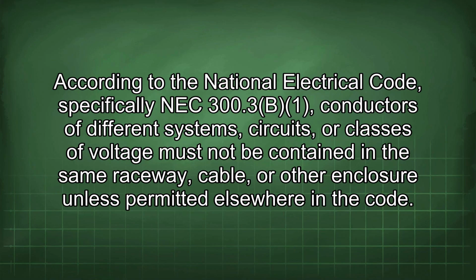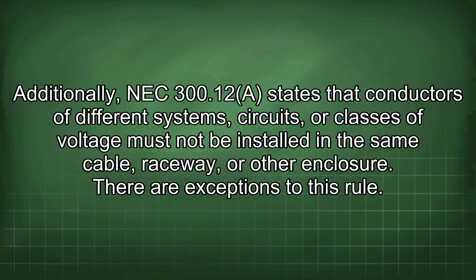According to the National Electrical Code, specifically NEC 300.3(B), conductors of different systems, circuits, or classes of voltage must not be contained in the same raceway, cable, or other enclosure unless permitted elsewhere in the code. Additionally, NEC 300.12 states that conductors of different systems, circuits, or classes of voltage must not be installed in the same cable, raceway, or other enclosure.